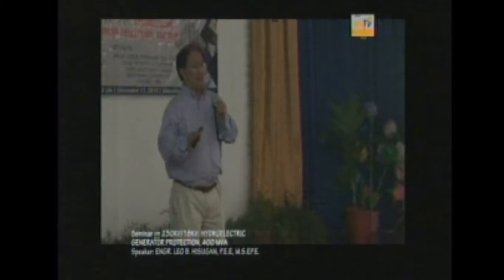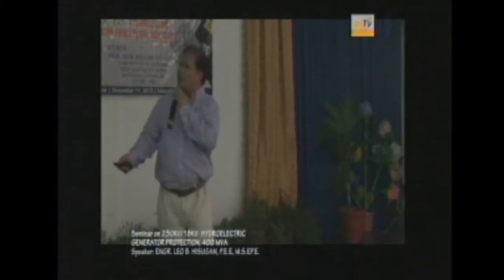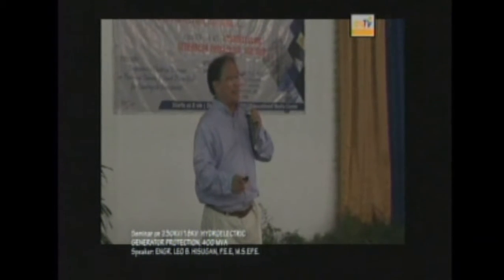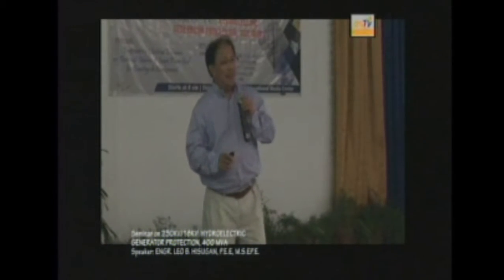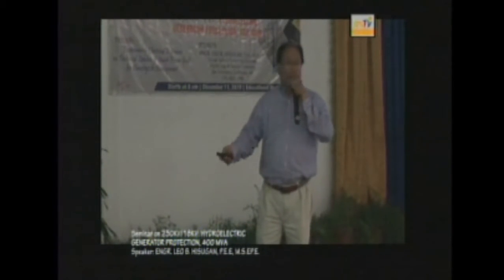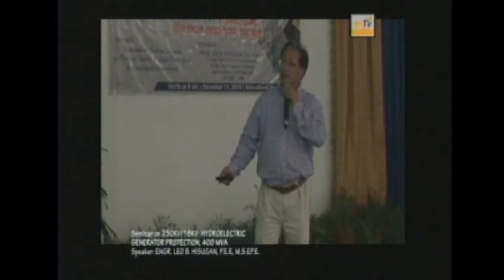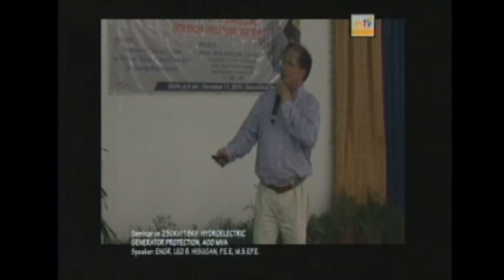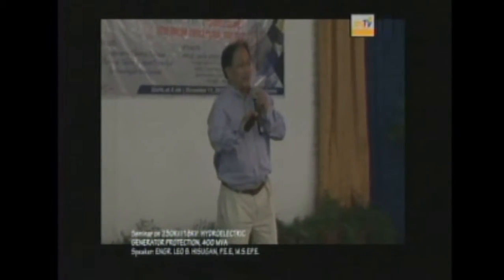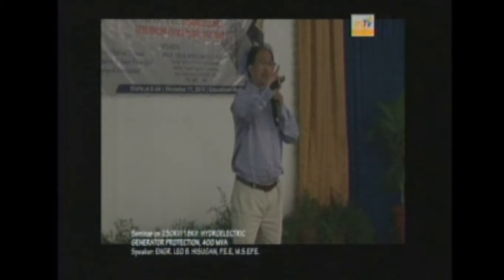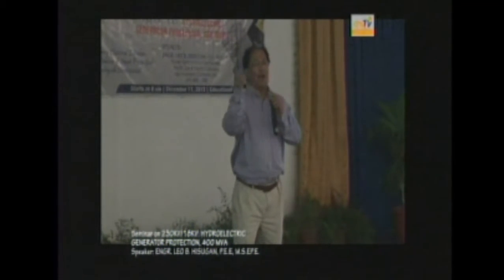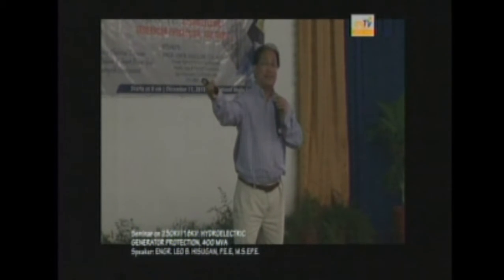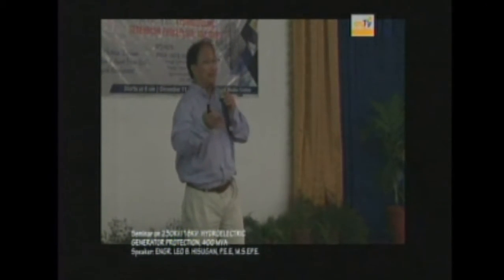Your generator, this hydroelectric power plant, has a high impedance grounding protection. And this high impedance grounding protection utilizes the distribution transformer. And this distribution transformer is normally rated like 75 kVA or 50 kVA. And the resistance here is across the grounding of the generators. There are normally 3 types of grounding in your generator. You have a high impedance grounding, a low impedance grounding, and also a hybrid grounding.